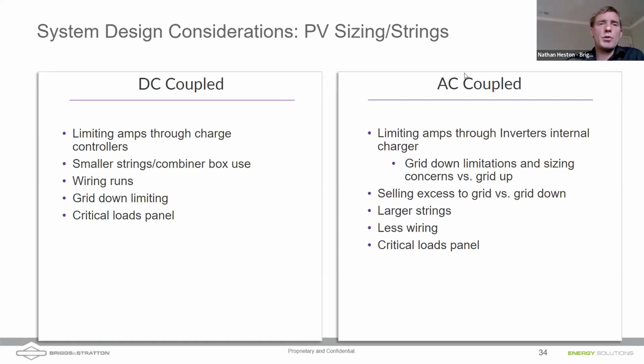So you do want to make sure, if you're doing a DC coupled design, that you're limiting the amps through the charge controllers to make sure that you're not sending more power into the batteries than they can handle. Batteries can only be charged so fast. Our batteries are rated at C/2, which means they shouldn't be charged faster than a 2-hour cycle, going from 0 to 100%. So you want to make sure that you're using equipment where you can limit those amps to the appropriate size for your battery bank.